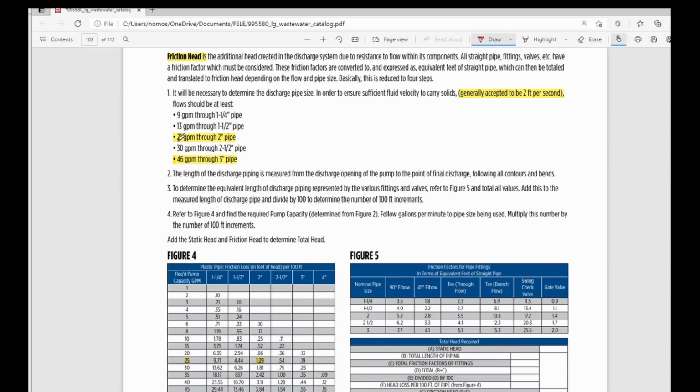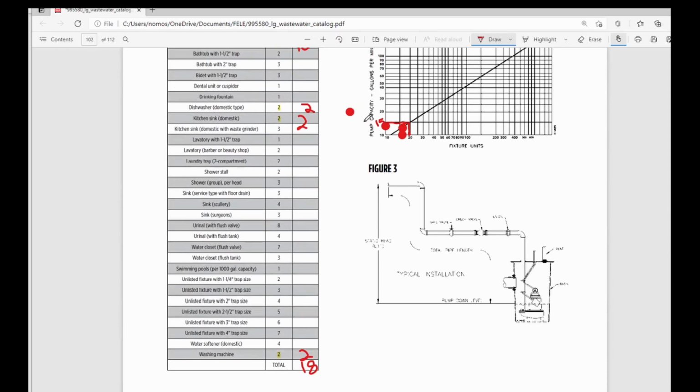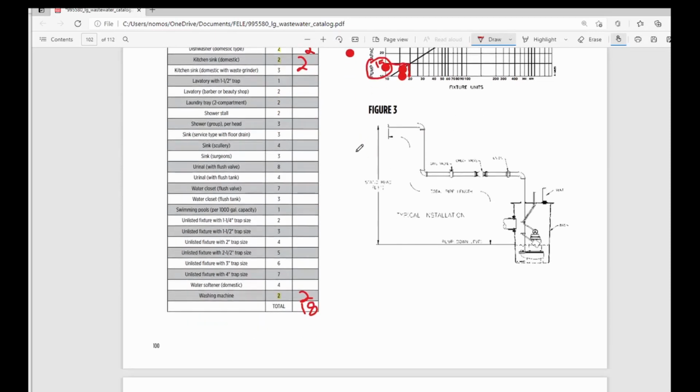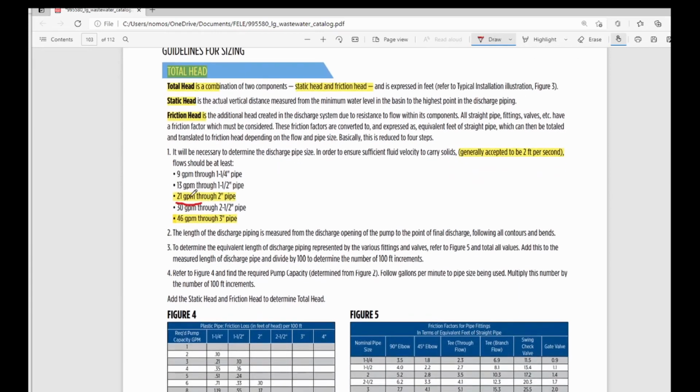And it's going to have to be 21 gallons a minute for my scouring velocity. So I'm going to use this flow rate at 21 gallons a minute so I'm matching scouring velocity, and I'm not going to use the 15 gallon a minute flow rate the chart gave me. Had it been higher than 21 gallons a minute, certainly I'd have had to go with it, but I didn't. So now I'm going to go with 21 gallons a minute.